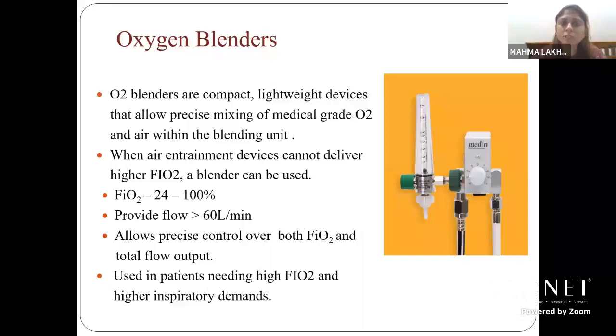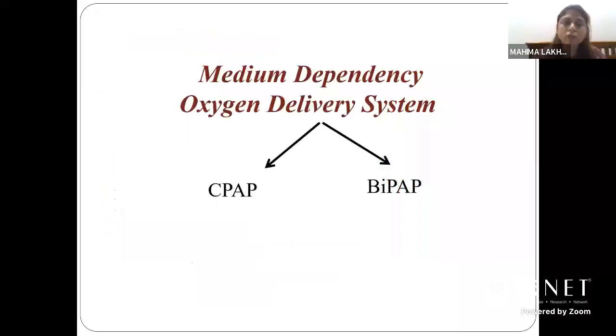Then the other method is oxygen blenders, which are compact, lightweight devices, and they allow the mixing of the medical grade oxygen with air within the blending unit. So when air entrainment devices cannot deliver a high FiO2, these blenders can be used. They can deliver a FiO2 up to 100%, and a flow rate of more than 60 liters per minute can be given. They allow precise control over both FiO2 as well as the total flow output. They are used in patients who need high FiO2 and have a high inspiratory demand also. So these were the low dependency oxygen delivery systems.